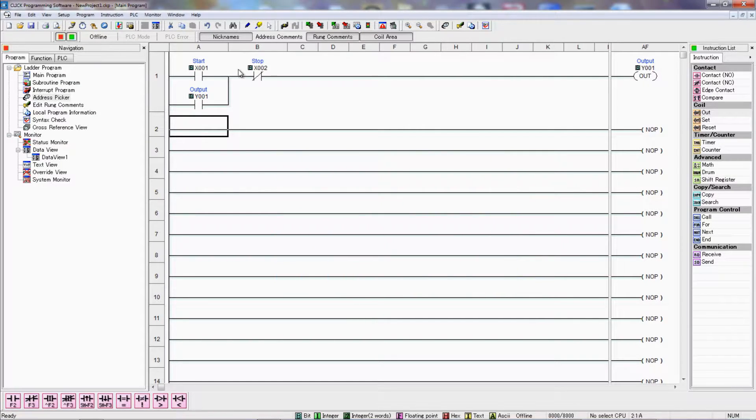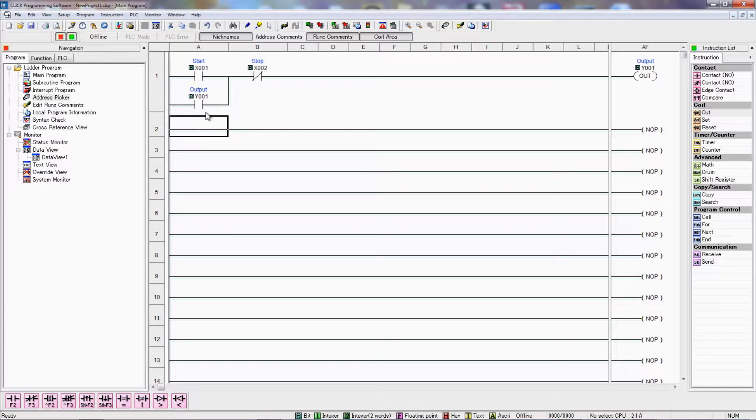So the start causes the circuit to latch on, or seal. The stop button, when that's depressed, will open this connection and cause it to drop out. And so this is directly controlling an on-off function where you get a momentary contact to control an output and latch it on just by that momentary button press.